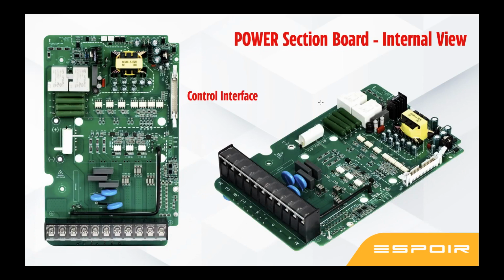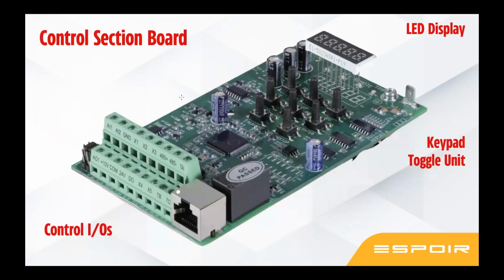So this is a power section board. You can see the terminal is given here. And this is the control interface, the white one where a ribbon cable comes. This is a power board of say a 5 HP drive. It changes from brand to brand. And this is the control section board. You can see these are the control IOs, Ethernet port, and this is a fault output relay. This is a keypad indicator, and this is a keypad toggle switch. The drive keypad sits on that and there is a switch inside, so when you press it, it goes inside. This is a toggle switch.